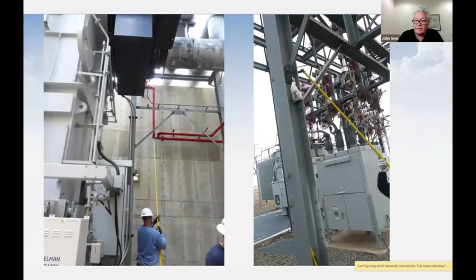So we had to get creative about what density we thought we needed, and you see multiple bags hanging together, because we couldn't hang them as close as we recommended. They wanted to protect that transformer, which the birds would hit. You see the phase bushings directly above the transformer. The birds would nest behind that and crap on the transformer and control cabinets below, creating all sorts of risk. That implementation stopped the problem, and they've never had any birds come back since.